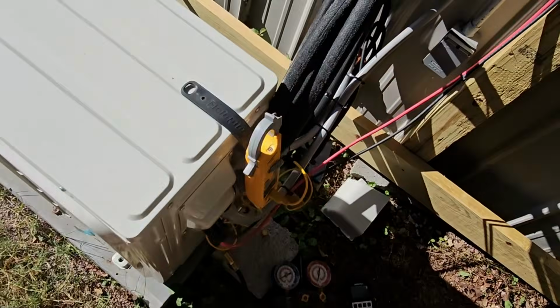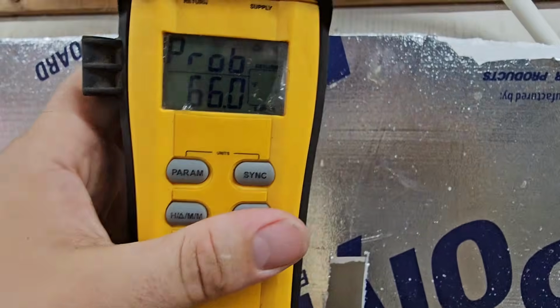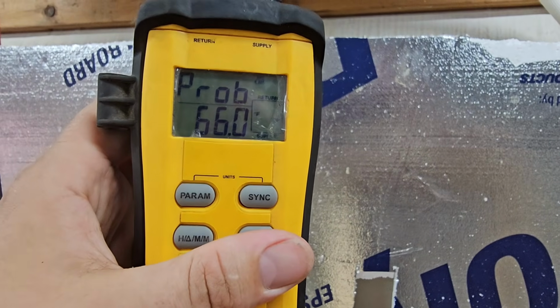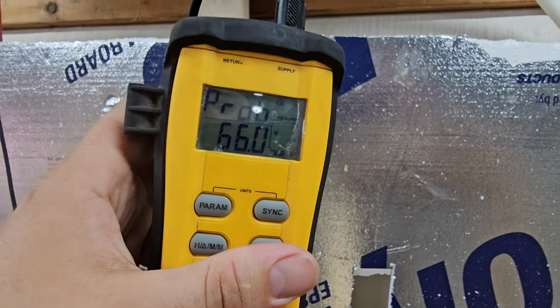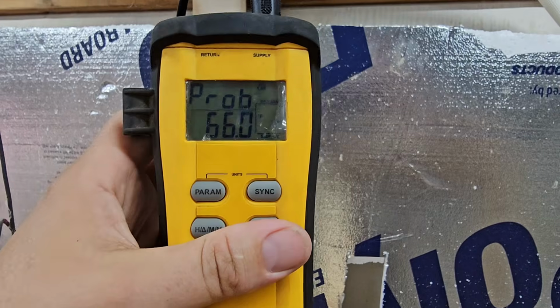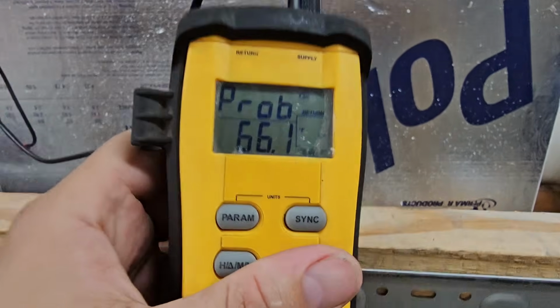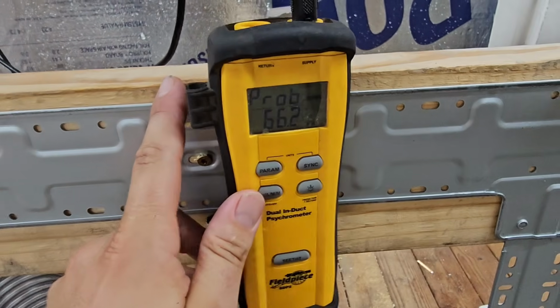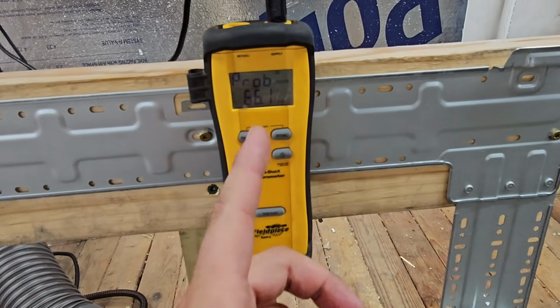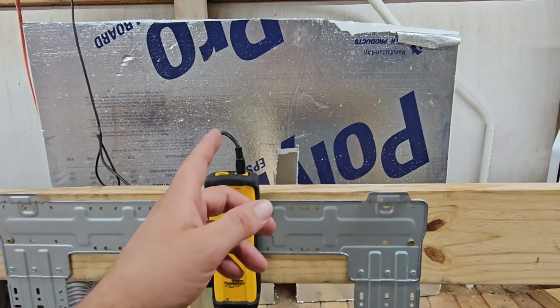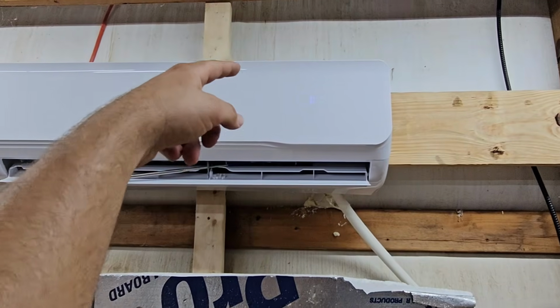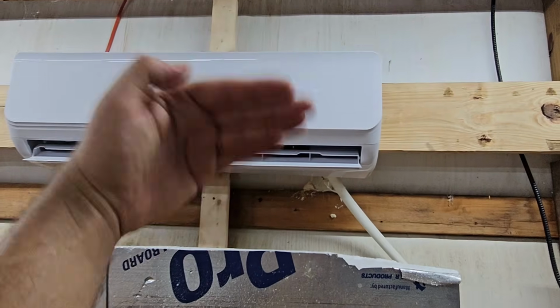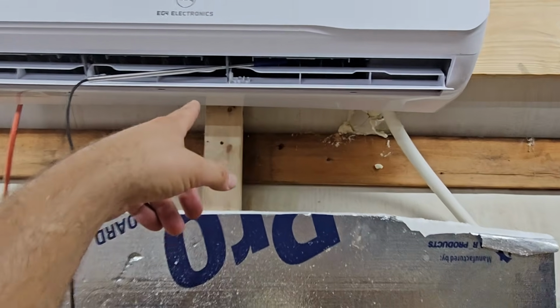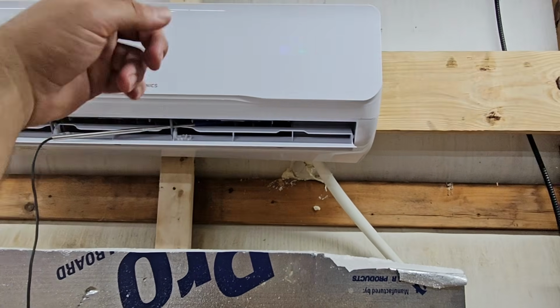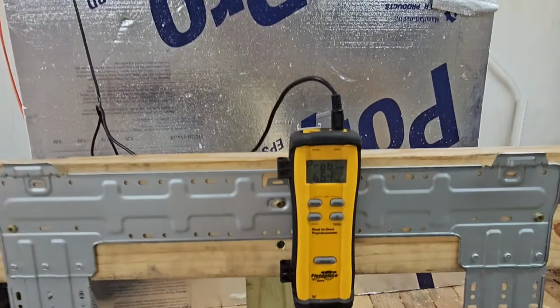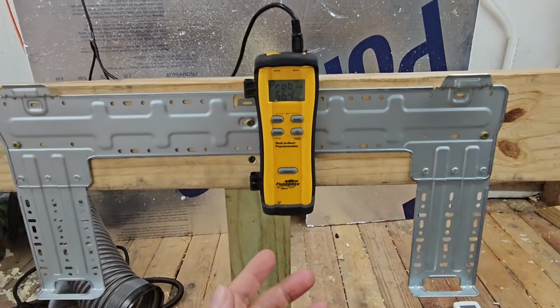Let's go look at the supply air temperature. Supply air temperature is 66 degrees. That's not very cold. I mean, that's good if it's 86 degrees in here, but it's not 86 degrees in here. So that is not good. That's not a good supply air temperature. You want to measure the temperature above where the unit sucks in the air. That's the return. And then you want to measure the temperature here, and you want to get at least a 20-degree difference between the two. 66 is not going to work for me.